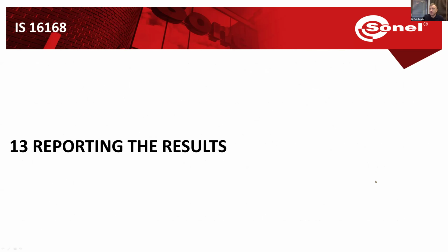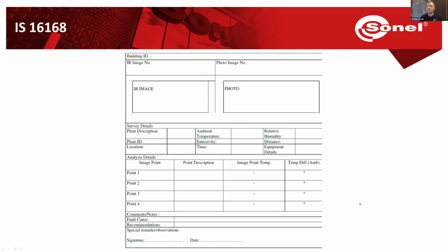And finally, the report. We can see in the standard a table that's an example of the report. We need to identify the building, enter image numbers, include the infrared image and the visual photo, details about the location, details about environmental conditions, and the analysis—this is in case we find any anomalies. We can add points, temperature values, and further comments describing what we've found. We can also determine the cause of the fault and make recommendations. Finally, the authorized personnel should sign it.